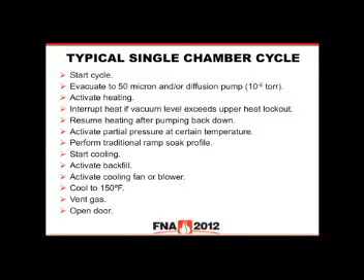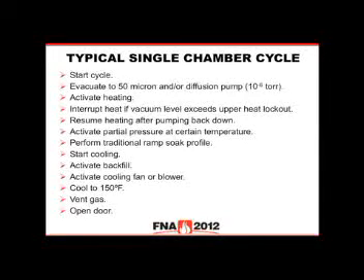Here is a typical single chamber cycle. You load the furnace cold, hit cycle start, and the system pumps down — perhaps to 50 microns. This is an adjustable setting; in the first system I showed you, that setting is in the vacuum instrument. So if you want to change it from 50 to 100 microns, you need to know how to get into the vacuum instrument to change a switch contact. Other systems might have the pump-down setting in the recipe.